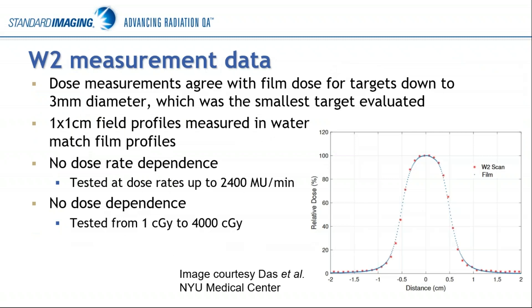You can also do point dose measurements — either for output factor measurements or directly measuring point dose. We've had people do it for patient-specific QA measurements for SRS treatments in a phantom like our Lucy phantom. A paper from Richard Popple's group at the University of Alabama Birmingham looked at dose measurements for stereotactic targets down to three millimeter diameter and compared their results with film, getting excellent agreement with the W2. A publication from Indra Das's group at NYU Langone also compared the W2 with film for small field scanning and looked at dose rate and dose dependence, with results behaving the same as the W1.